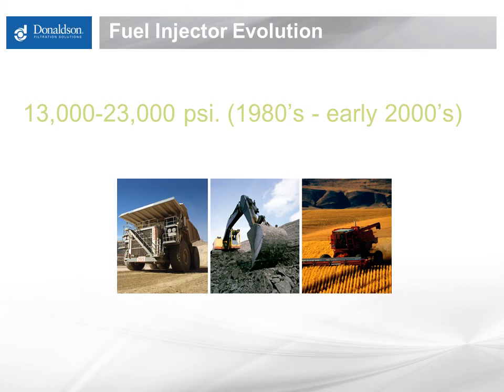These systems were also still quite tolerant of fine particulate. These fuel systems only needed reasonably good protection from particulate 7 to 10 microns and larger — think of something about the size of a red blood cell. These engines were long considered able to burn just about anything, including blending in used oils, blends of residual fuel oils and diesel, some home heating oils, jet fuel, etc.